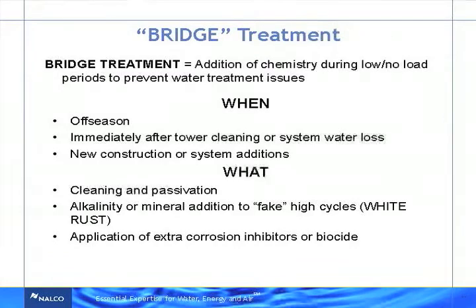And what you can do is what I call bridge treatment. So basically, bridge treatment is an addition of chemistry during low or no load or commissioning times during new construction periods to prevent the water treatment issues from occurring. So you want to do it in the off-season, after your tower cleaning, new construction or system additions. Basically what it is, first of all, clean and passivate all the systems. I can't stress that enough. Make sure the systems are clean before you put them online with the rest of your system so you don't pollute them. What you can do is fake high cycles.